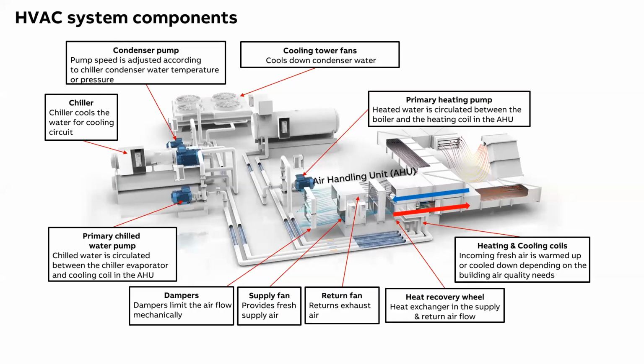Now, moving ahead. Irrespective of these segments, in terms of the application typically in HVAC, if we talk about the VFD, then a VFD can be used in general in any application wherever there is a motor. Now, what does a VFD do? One, it helps in starting and stopping. It gives the traditional role of a starter, as well as it controls the process. It helps in achieving automation in terms of the precise speed which is required, and in turn saves energy.